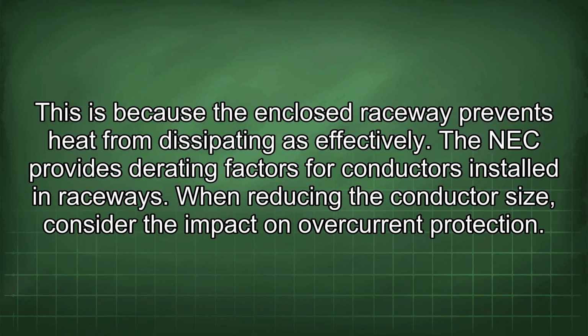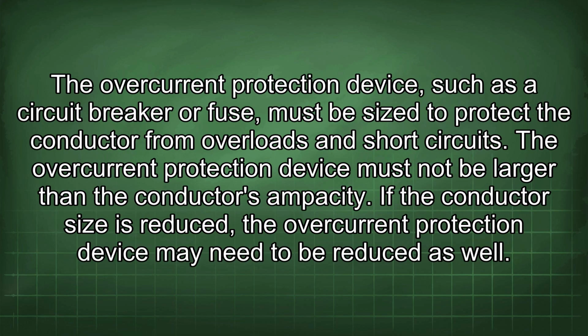When reducing the conductor size, consider the impact on overcurrent protection. The overcurrent protection device, such as a circuit breaker or fuse, must be sized to protect the conductor from overloads and short circuits. The overcurrent protection device must not be larger than the conductor's ampacity. If the conductor size is reduced, the overcurrent protection device may need to be reduced as well.